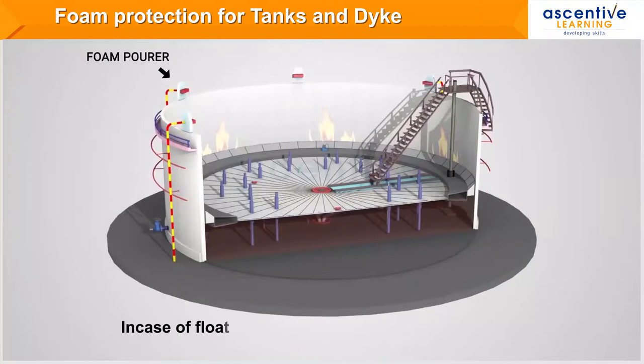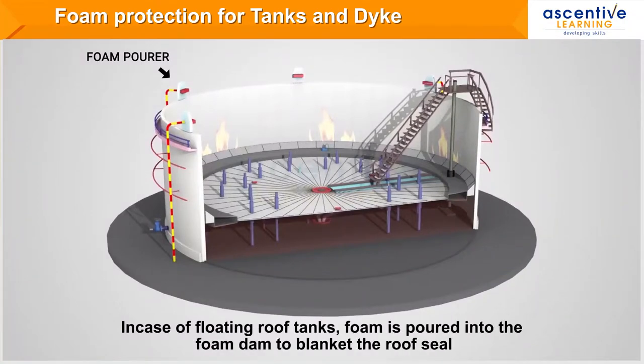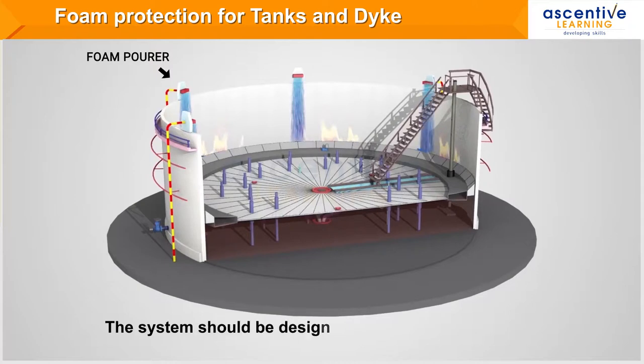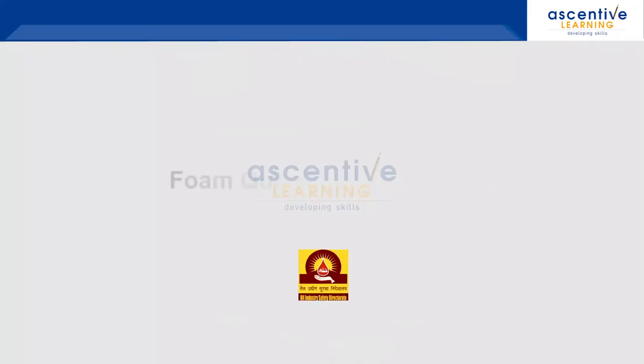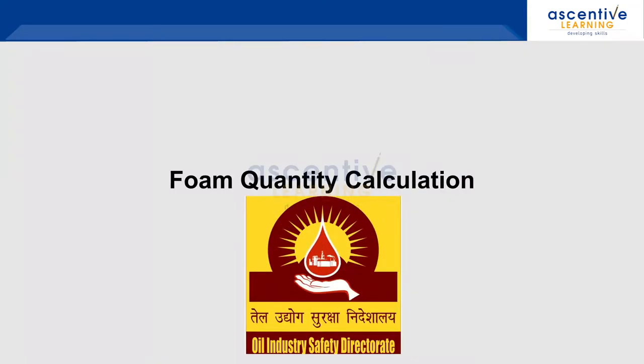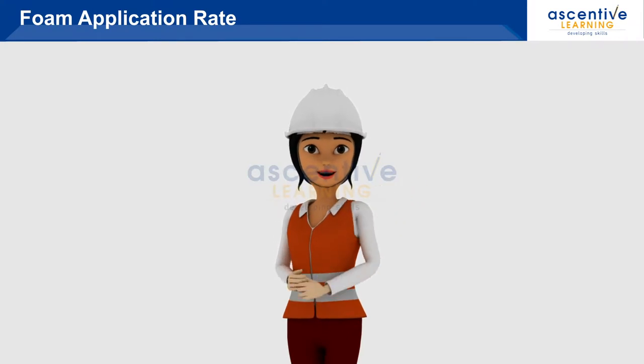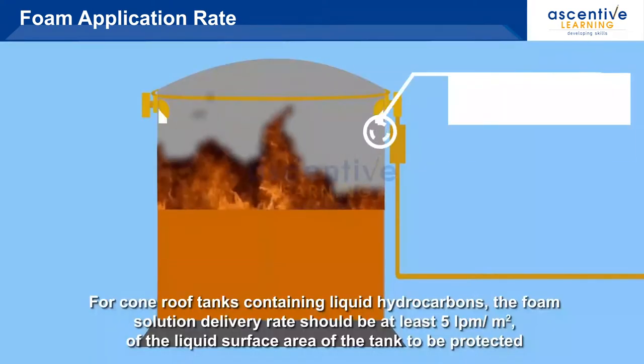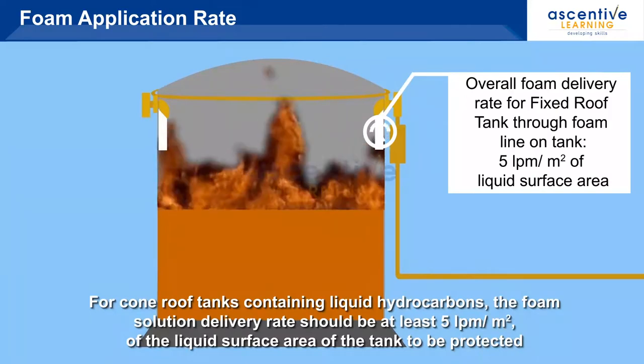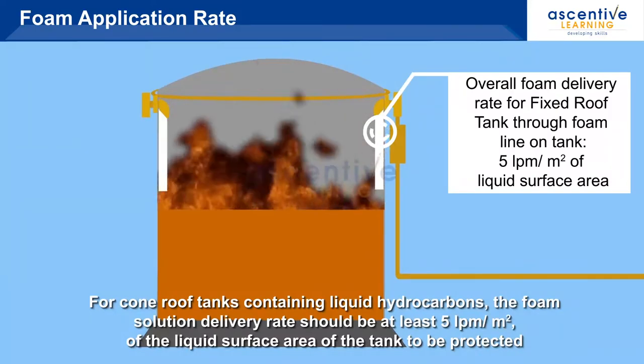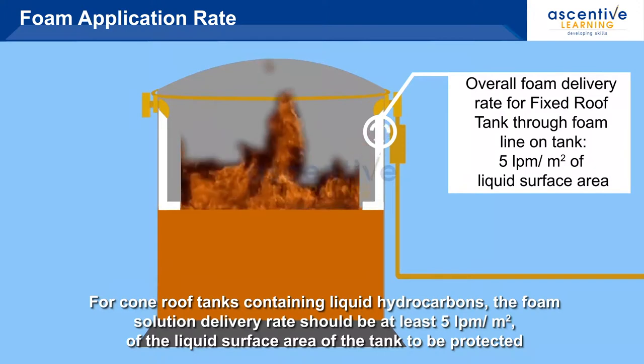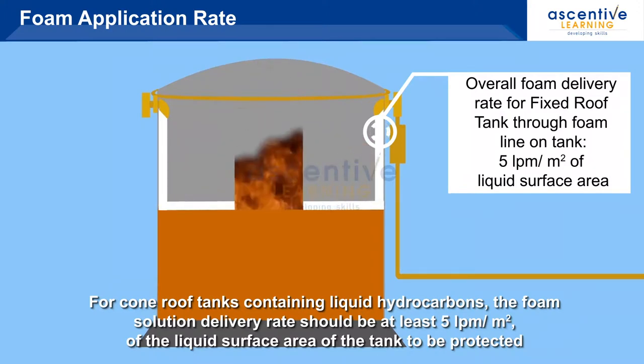In case of floating roof tanks, foam is poured into the foam dam to blanket the roof seal. The system should be designed to create a foam blanket on the burning surface in a reasonably short period. For cone roof tanks containing liquid hydrocarbons, the foam solution delivery rate should be at least 5 liters per minute per square meter of the liquid surface area of the tank to be protected.